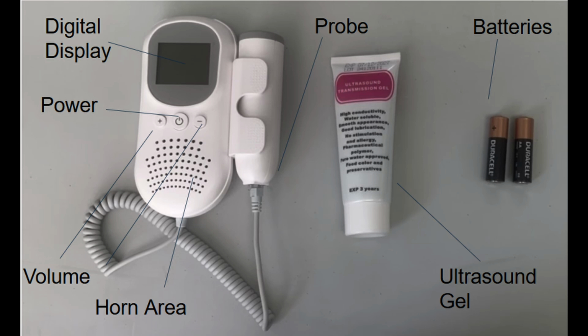The primary components of the device include the base unit and the probe. The base unit contains many essential controls and displays, such as the digital display area, which shows live heart rate data; volume buttons to increase or decrease the volume; the power button to turn the device on and off; the speaker area, where the audible output signal is emitted; the earphone jack, which allows for private listening; and the probe connection port, where the probe connects to the base unit. And the probe. The standard probe operates at 2 to 3 MHz frequency, allowing detection of fetal heartbeat.